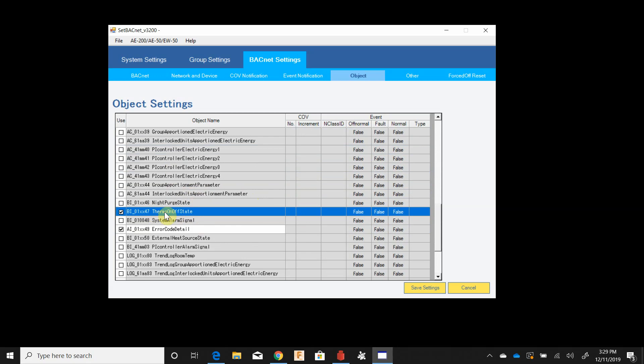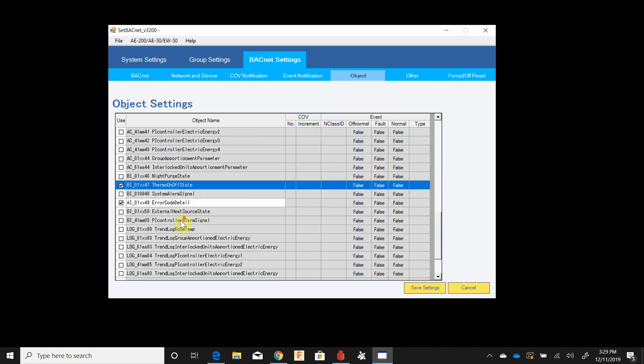Thermo on off state I would always check this one. This tells you whether or not the fan coil is actively heating or cooling. Doesn't tell you which mode it's in, doesn't tell you what it's trying to get, but it will tell you if it's actively calling or not.